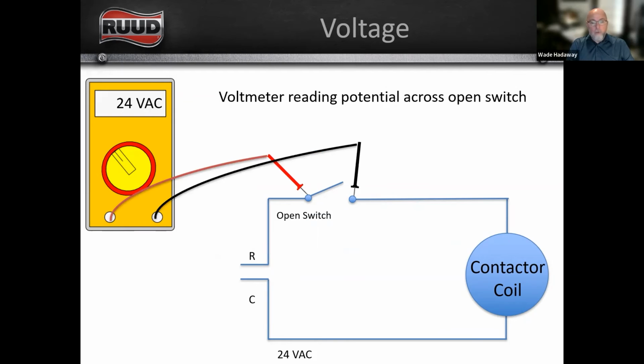So if you check across an open switch, just like I was saying earlier, you're going to read the voltage potential. A lot of times people mess this up, especially when they're reading voltages across a thermostat. Reading 24 volts across a switch tells you that that switch is open. If the switch is closed, you should not read any voltage. You shouldn't have voltage drop across a closed switch. It might be very, very minute, but any voltage drop that you have across that switch is telling you that you have resistance there in that switch. And that switch could be a set of contacts. We're going to talk about that here in just a second.